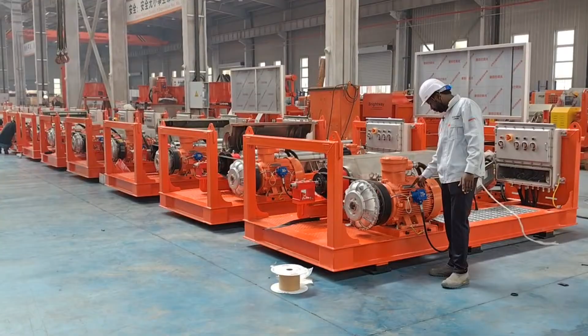As you can see, this one is also explosion-proof, with a capacity of 37 kilowatts, a voltage of 460 volts, amps of 58.9, rotation speed of about 1,776 revolutions per minute, a frequency of 60 Hz, a power factor (cos phi) of 0.87, and an IP rating of 55.